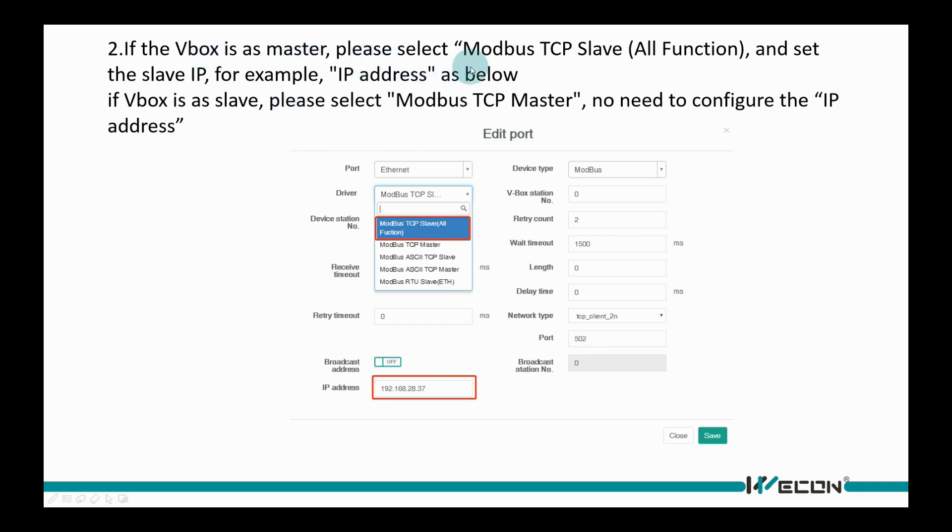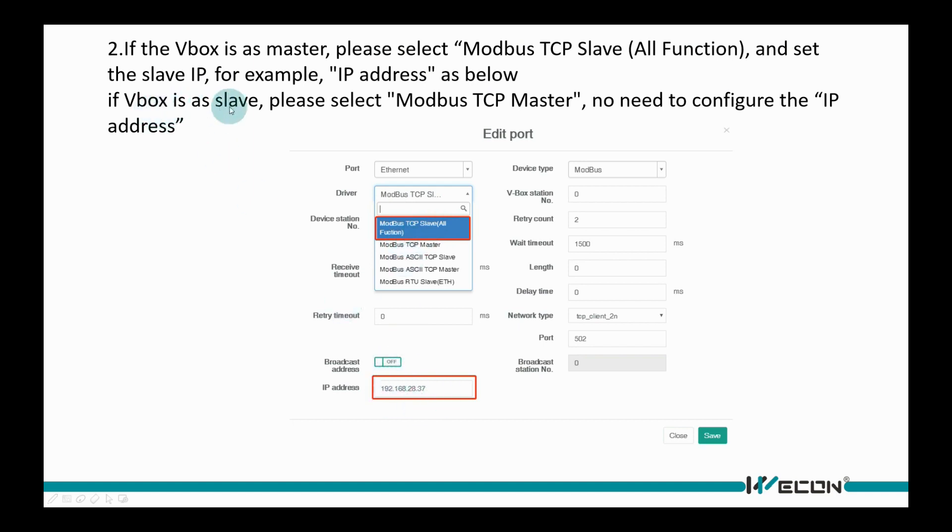If the VBOX is as master, please select MODBUS TCP slave all function and set the slave IP. If VBOX is as slave, please select MODBUS TCP master, no need to configure the IP address.